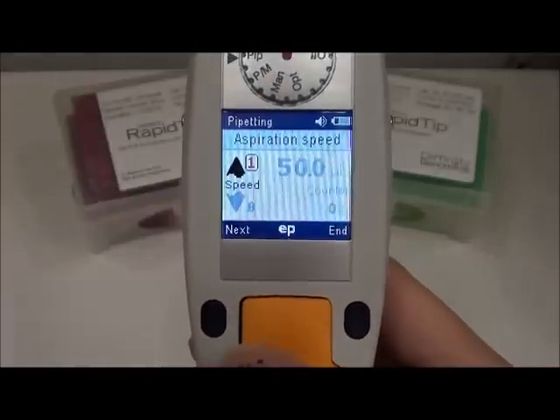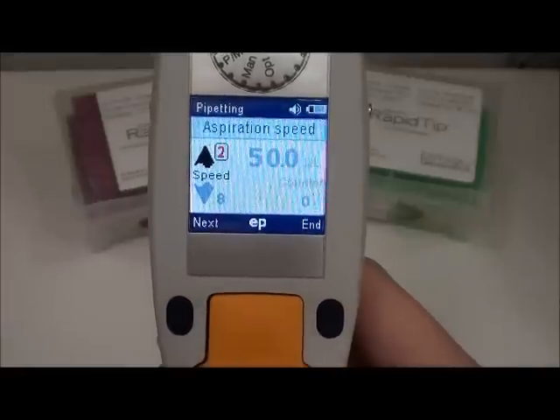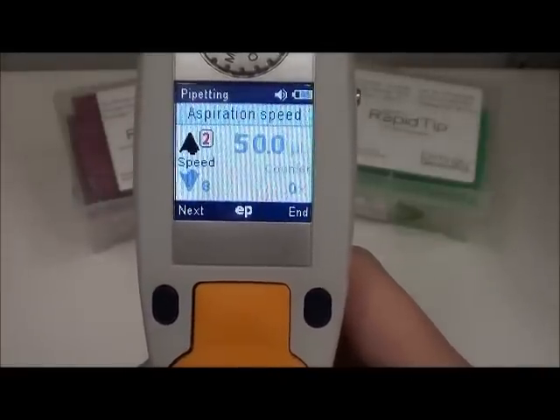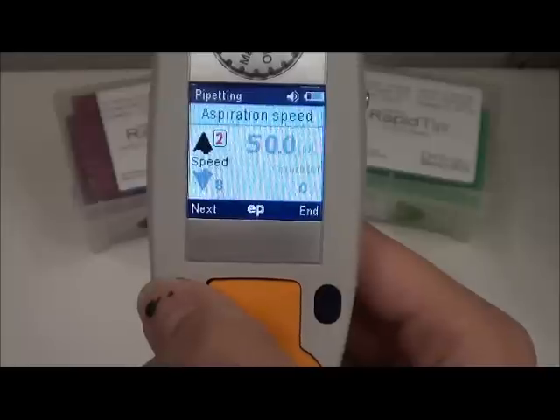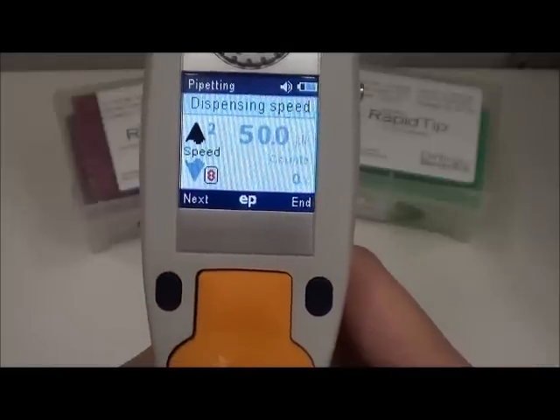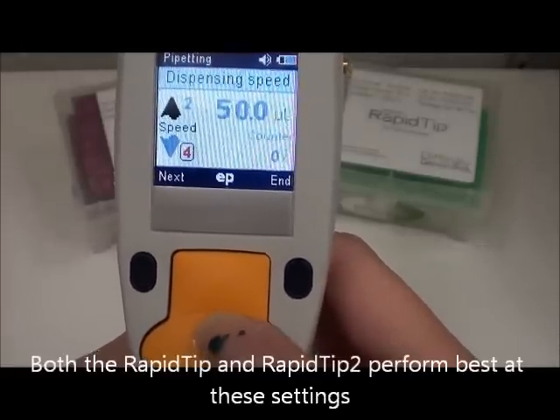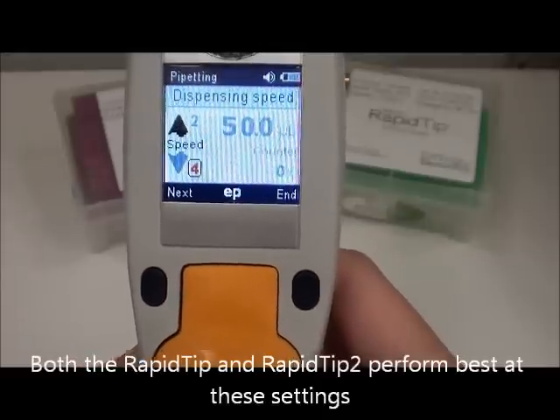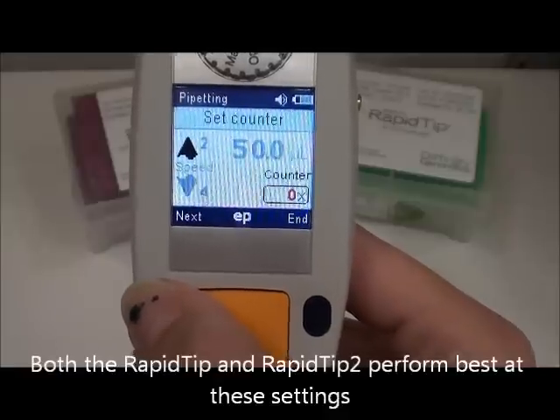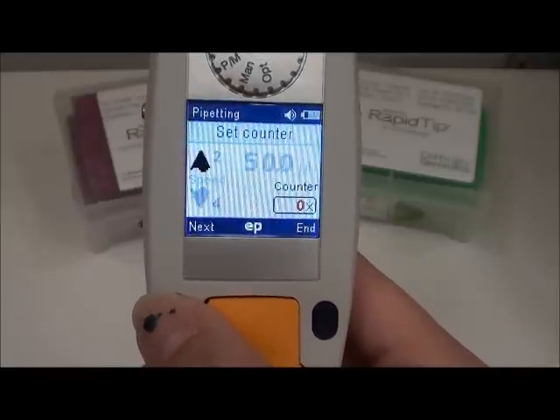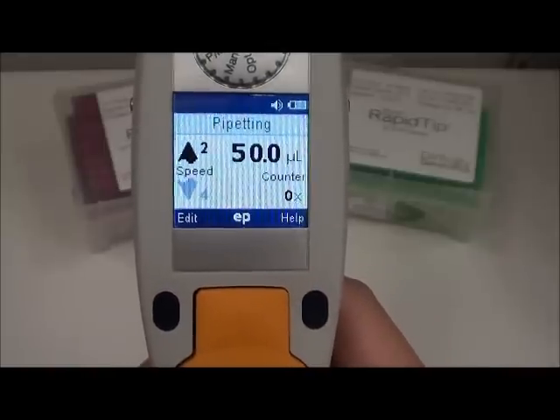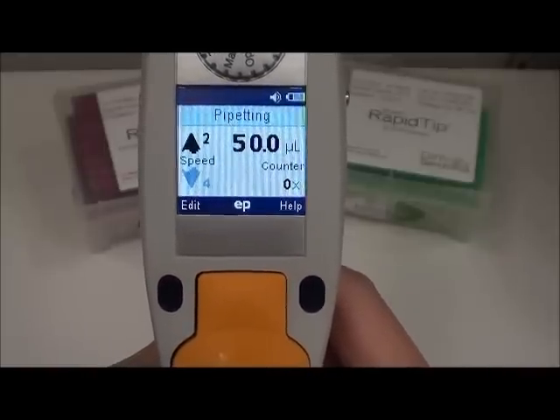Then we can hit next and it'll highlight the aspiration speed. Right now we have it at 1, and the highest is 8 — we think that 2 is one of the optimum speeds to aspirate with. So we're going to leave it at that and go to next. Since the highest speed you can do is 8, I think 4 is a good dispensing speed for that. We're going to go next again, and it highlights the counter, which we're going to leave at 0, and hit end. It saves our changes, and now you'll be ready to pipette up and down.